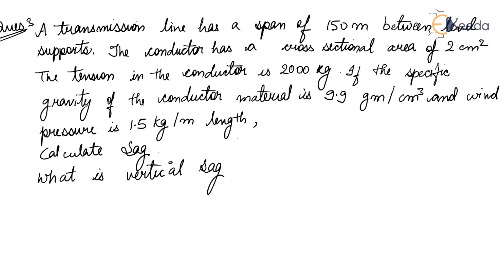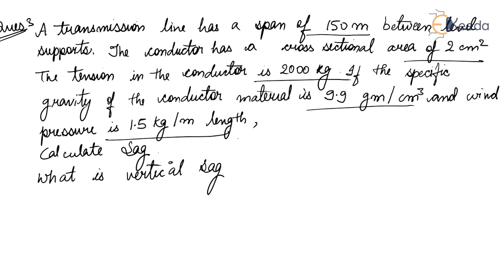The numerical is: a transmission line has a span of 150 meters between level supports, so L = 150 m. The conductor has a cross-sectional area of 2 cm². The tension in the conductor is 2000 kg. The specific gravity of the conductor material is 9.9 g/cm³ and wind pressure is 1.5 kg per meter length. We have to calculate the SAG and the vertical SAG.